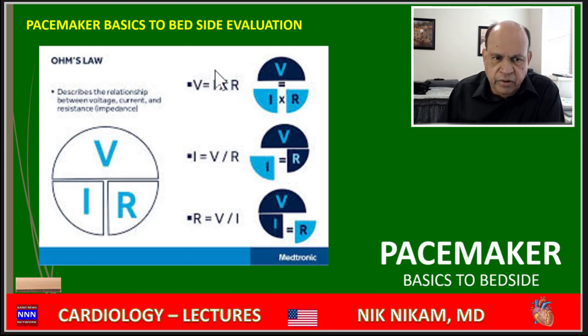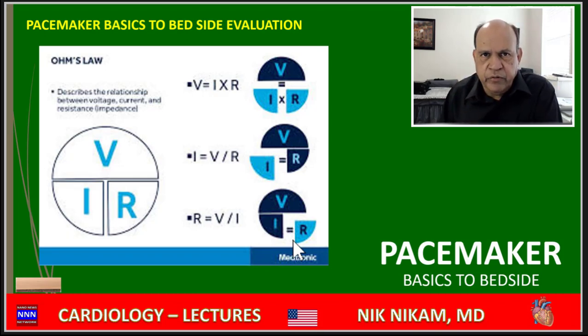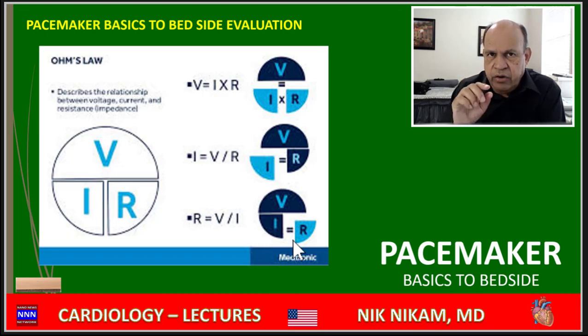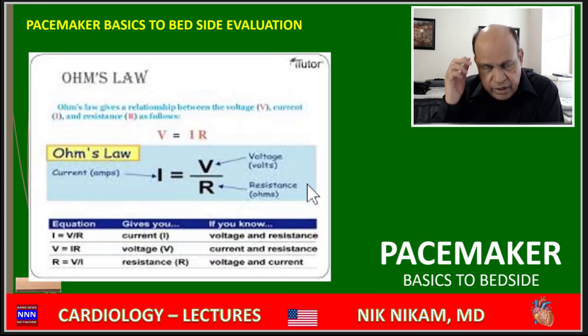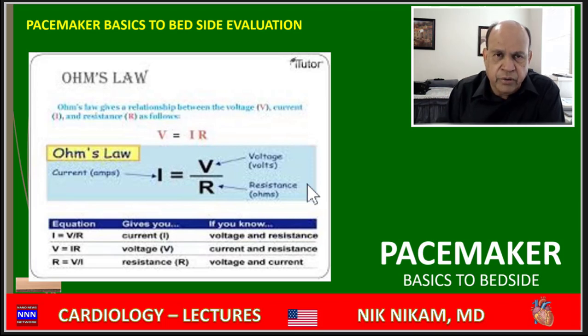So we know the electrical voltage, we know the current, and we can always find out the resistance. The resistance is something that is created by the pacemaker wire. If it's not in good contact, the resistance goes up. If there are leaks in the pacemaker leads due to breakage, then the resistance goes down. And that determines how much current is used by that pacemaker to activate the atria or the ventricle.